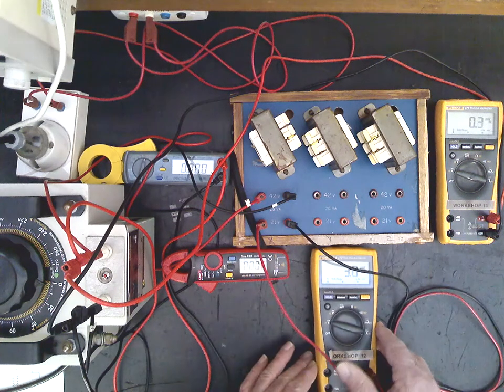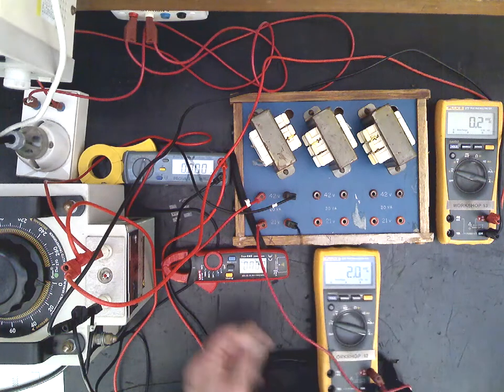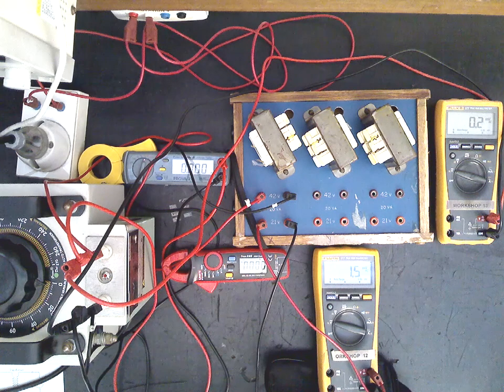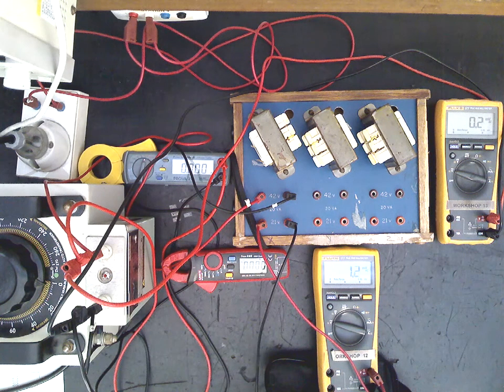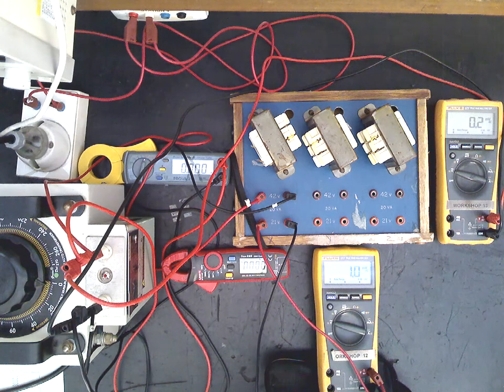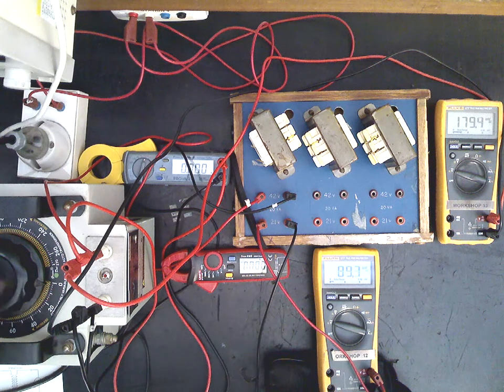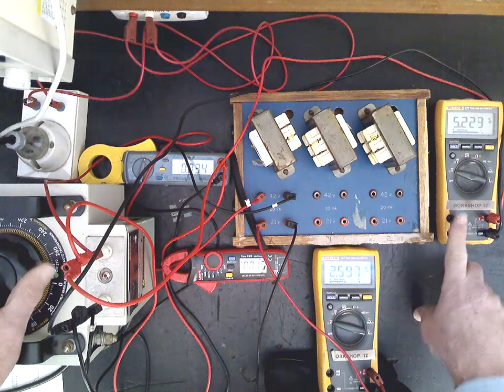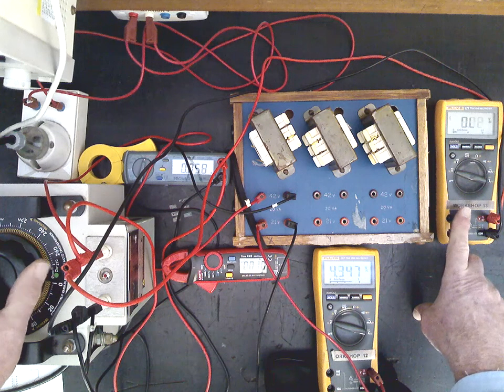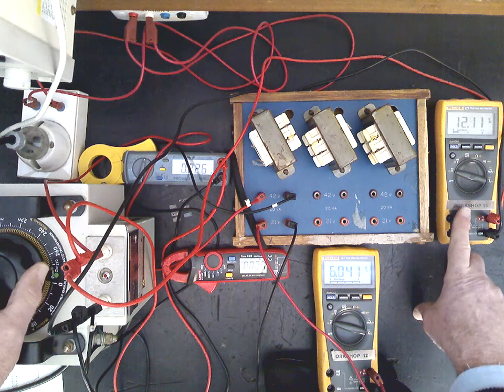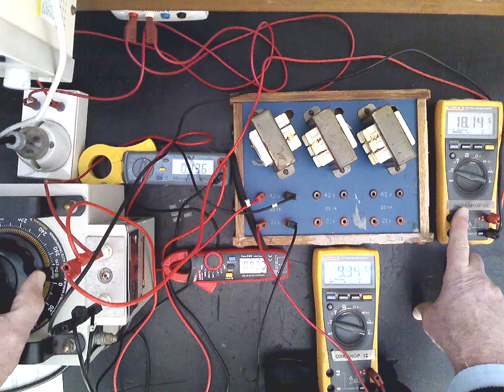Let's tilt that up so you can see the screen a bit better with the results there. So that's basically a circuit connection for the open circuit test. And we need at that point is to turn your supply power on. And watch your primary voltage come up to rated primary voltage, which in this case is 42 volts AC.